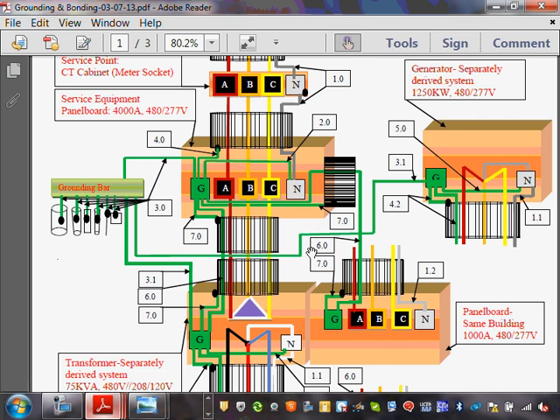So that summarizes the 12 chapters of grounding and bonding in one sheet. Any comments? Any questions? Any corrections? I can't emphasize the separately derived system enough, guys. If it's a non-separately derived system, then this number 5 disappears, and you have to pull the neutral all the way there. If your circuit breaker is here, then this is the equipment grounding conductor. If your first circuit breaker is here, then this piece is called a supply side bonding jumper.